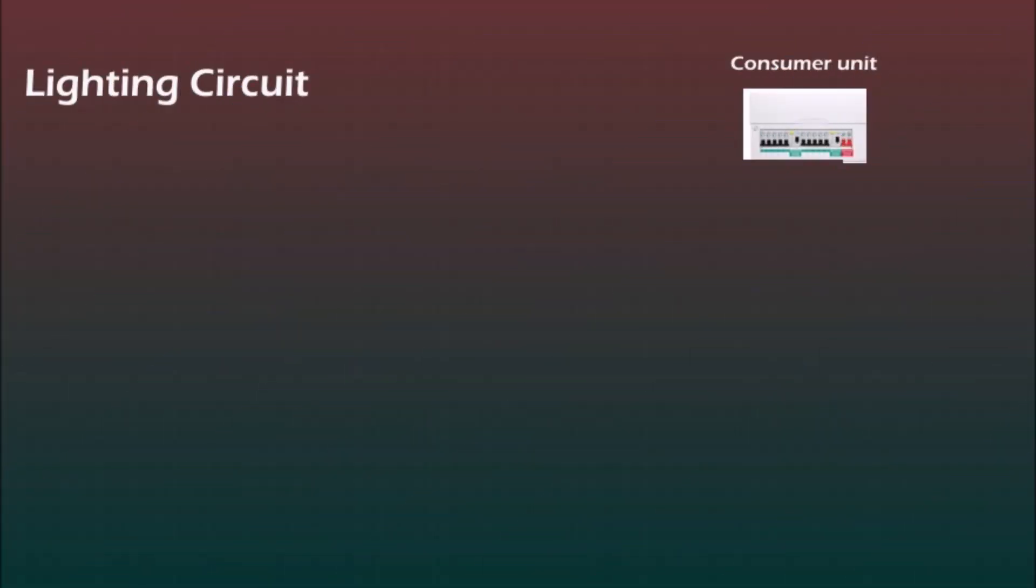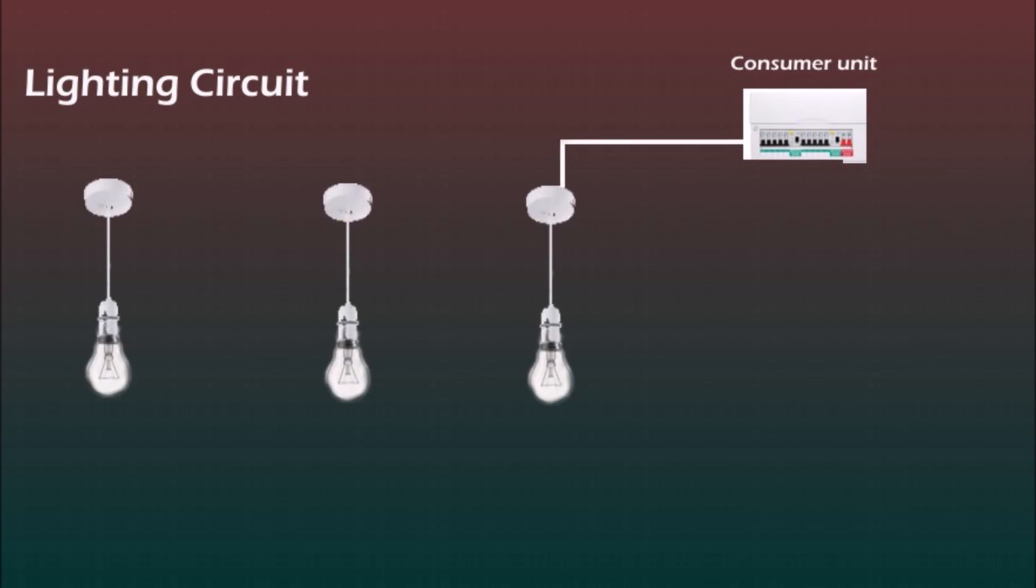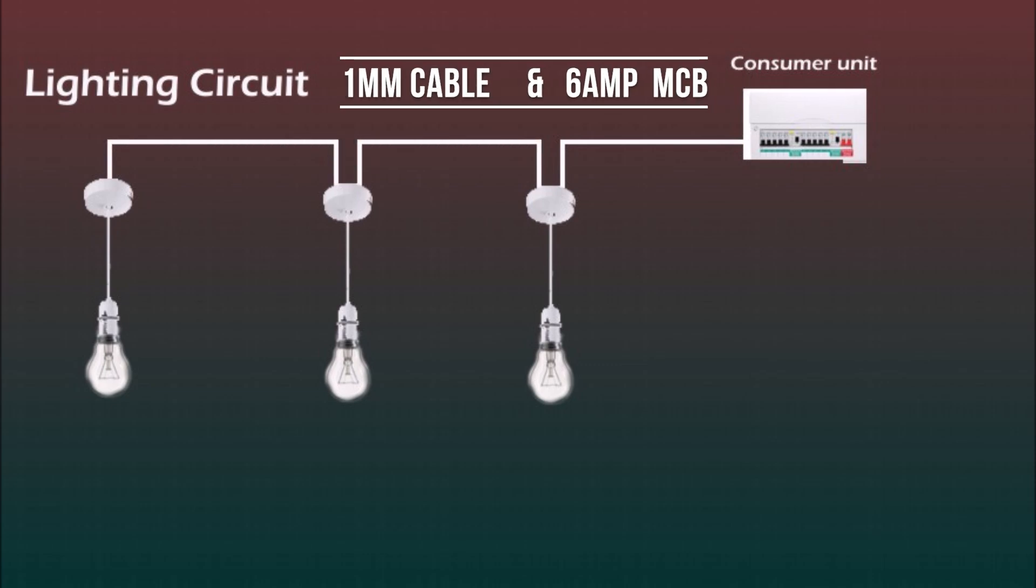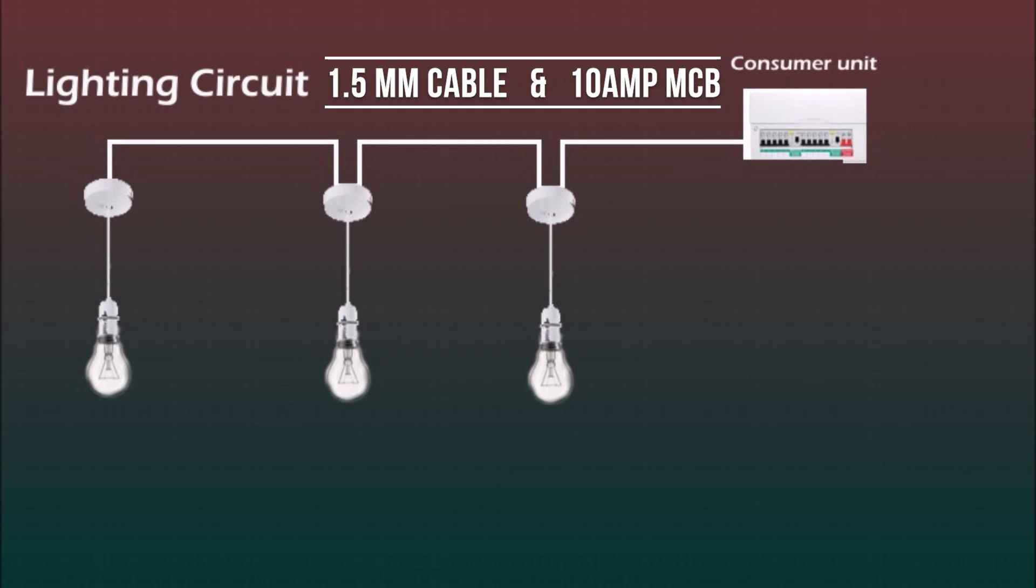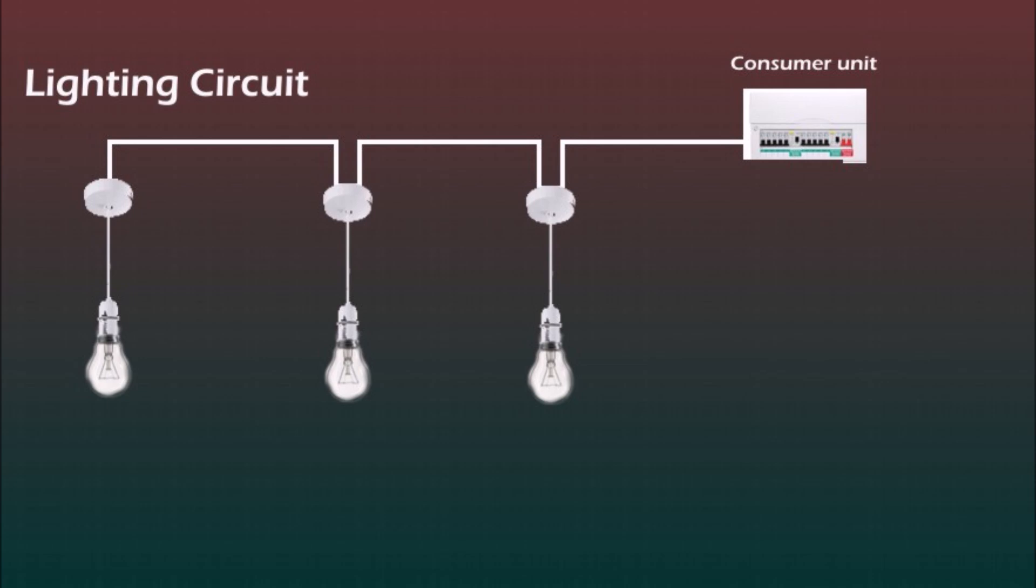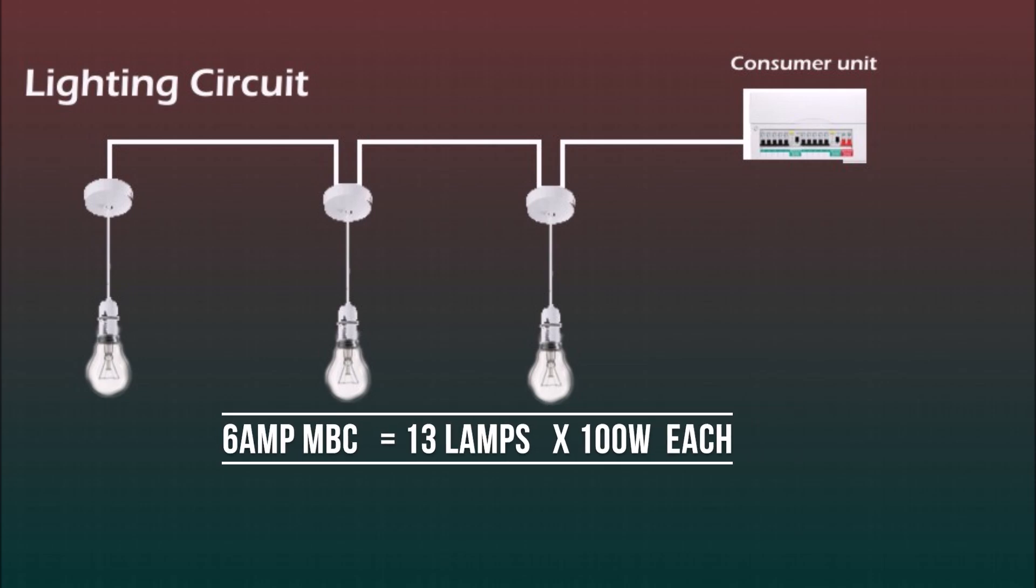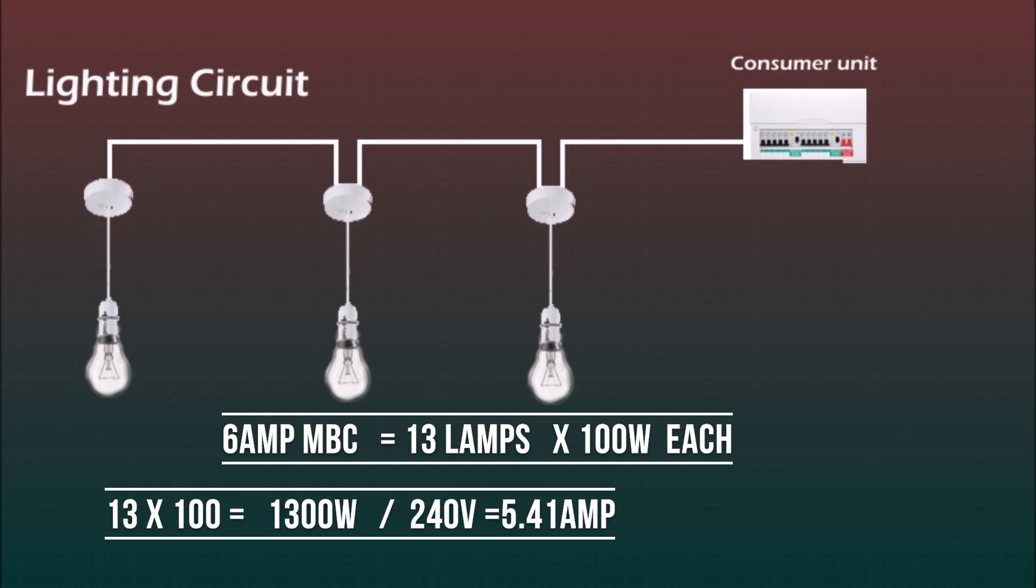So the next circuit that I want to explain is the lighting circuit. Lighting circuits are always radial, they start at the consumer unit and finish at the last point. Usually 1mm cable and 6 amp MCB is enough for domestic installations, unless you've got a really long circuit. Then 1.5mm cable and 10 amp MCB is recommended. On a 6 amp MCB you can run 13 lamps with 100 watts bulb at each lamp. Obviously reasonably is to connect only 10 lamps. But nowadays most people use LED lights and these are rated around 5 watt each. So the total load is very unlikely to exceed the rating of the MCB or the cable.